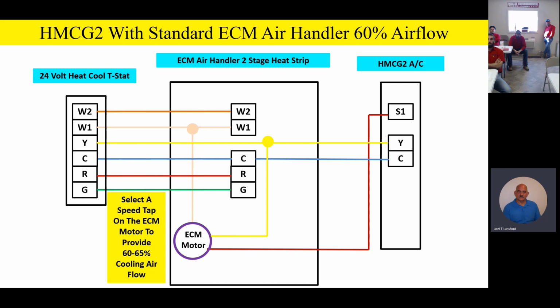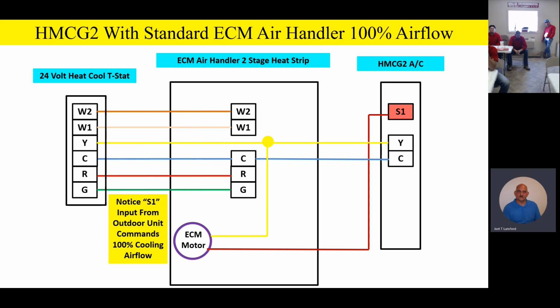You'll notice that the Y terminal is going to come down directly to the motor. Anytime we call for compressor operation, the Y terminal is going to command that 60 to 65% airflow. So when you take a look at the straight cooling product, standard airflow, just sitting there, is going to be 60 to 65% airflow. So when this unit comes on, it's automatically going to default to the lower airflow. Then when I get an S1 call from the outdoor unit, that 24 volt signal goes inside and commands 100% airflow. It's exactly opposite of the heat pump, and there's no relay at all. Are there any questions or comments on how that scheme works?